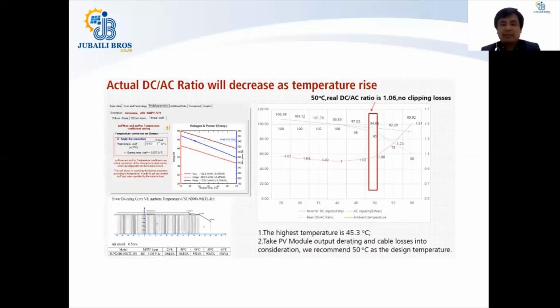In the Middle East, you can see that the temperature goes up to 45.3 degrees Celsius. Now, taking PV module output derating and cable losses into consideration, we recommend that you design your PV systems for 50 degrees Celsius.